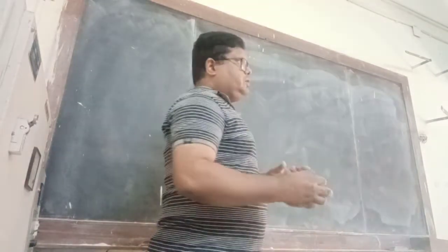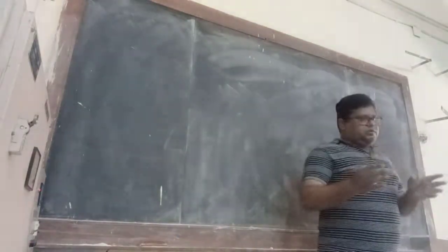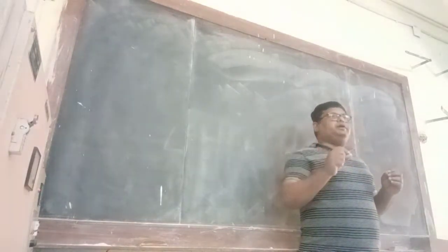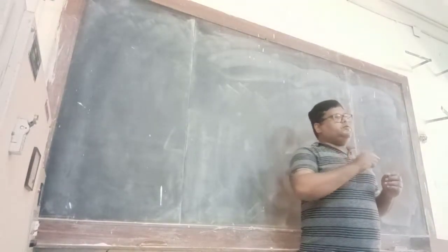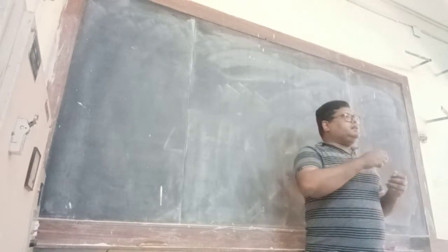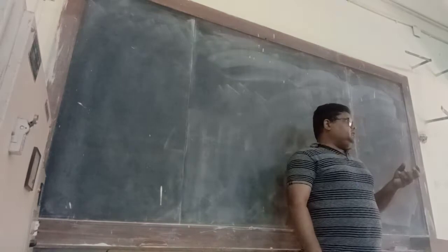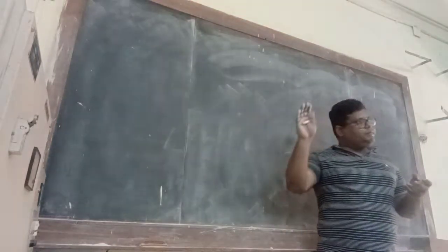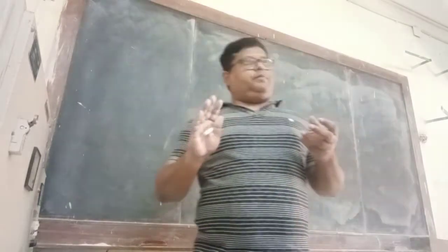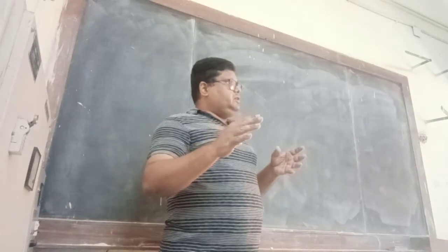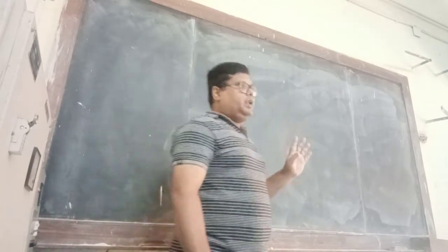Using this GM counter, you put the GM counter in one place. The first thing you did was to find the operating point of the detector. For that you started biasing the detector, slowly increasing the voltage, and then you measured the count after putting a source close to the GM counter. As a result you obtained a plateau, and from the linear part of it you obtained your operating point. You set the operating point such that if there is a fluctuation in voltage, it doesn't affect your count rate. This is the overall idea.